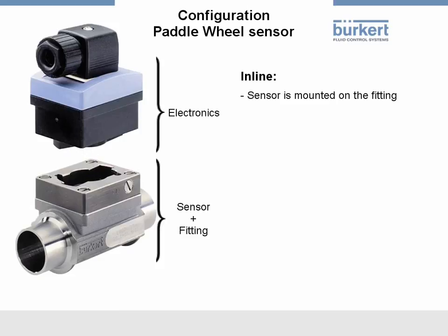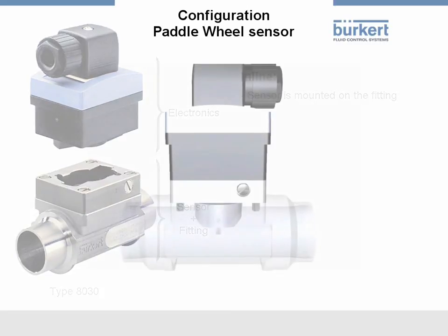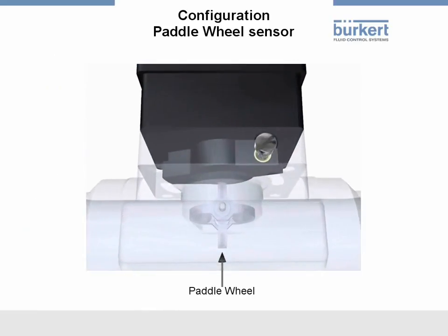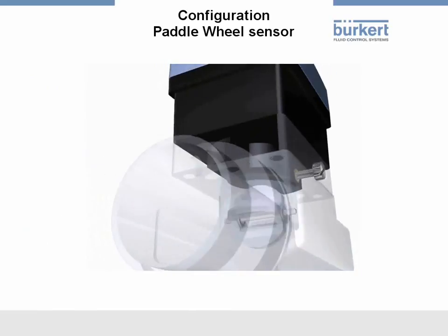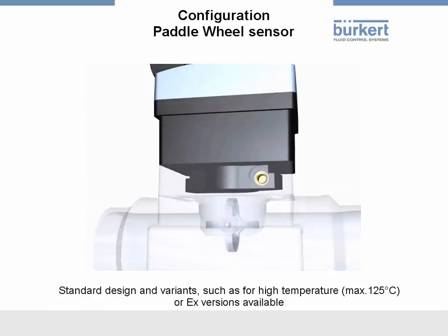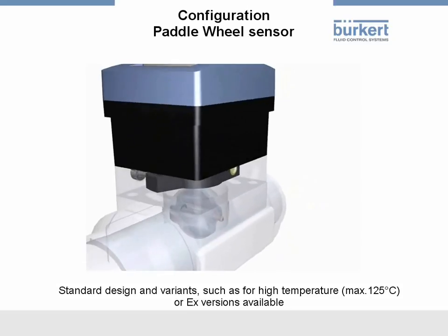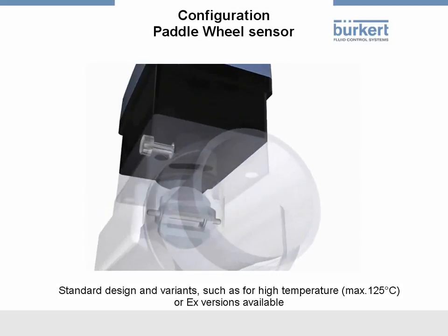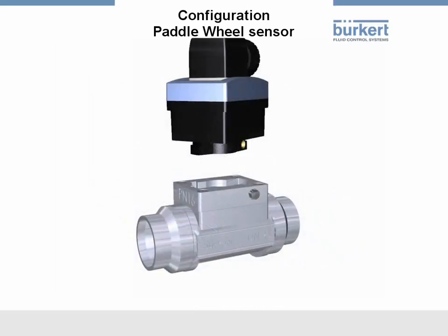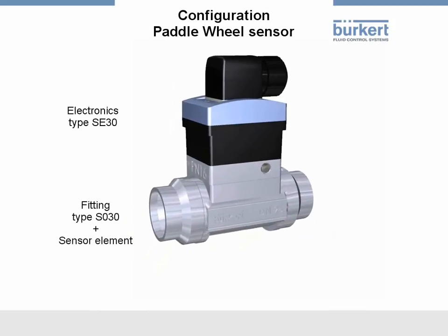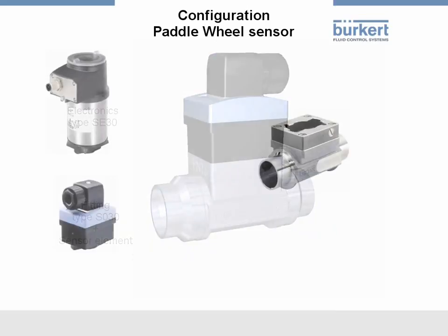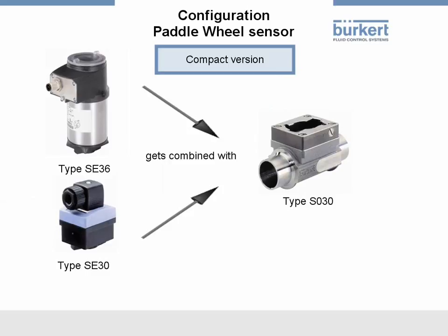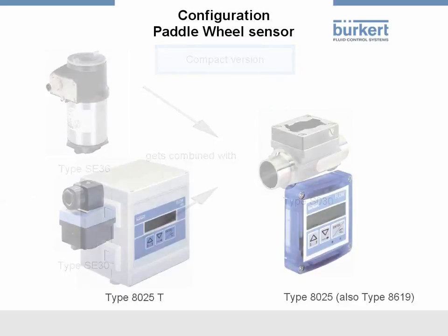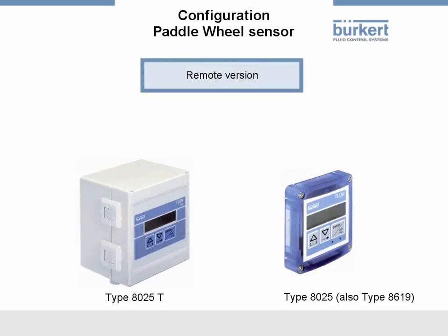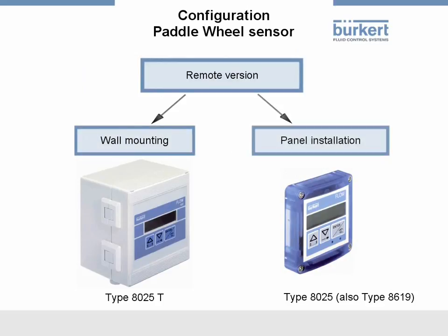Transfer of the measuring signal to the electronics is contactless, for example, optical or magnetic. The primary sensor element, a bearing-mounted paddle wheel, is therefore directly within the fitting and is set into rotation by the flowing fluid. Besides the standard design, there are variants, such as for high temperature, or Ex versions that are approved for use in explosive areas. The electronics are mounted on the combined fitting and sensor element. There's a compact version, for example. Alternatively, it's possible to connect the unit to remote electronics. For the remote version, there's the option of wall mounting or panel installation.